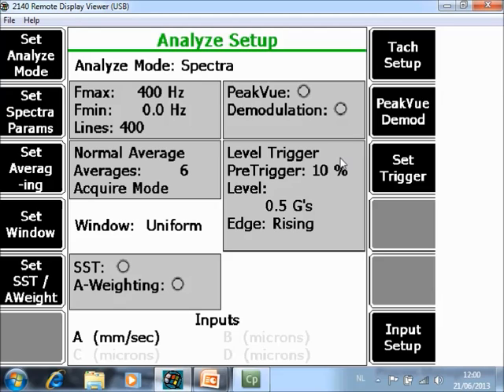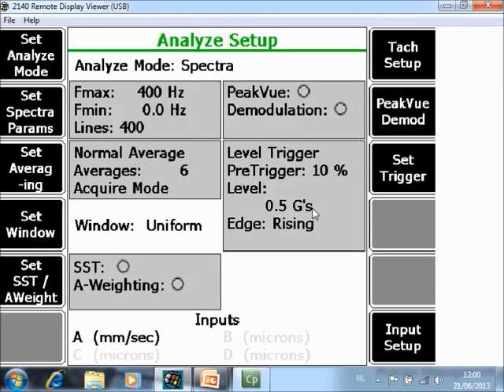But what is very important is the trigger level here. The default value is 0.5 G's. That means that as soon as you start data collection, the data collector is in a kind of a wait mode. And as soon as he feels a vibration level higher than 0.5 G's, he will consider it as an impact and he will store the data.